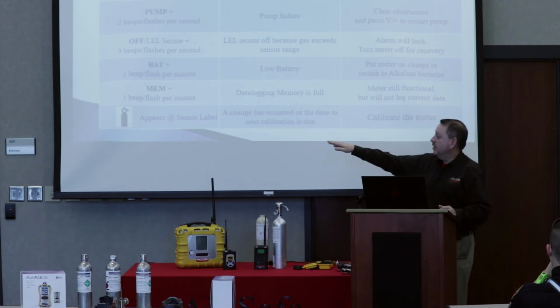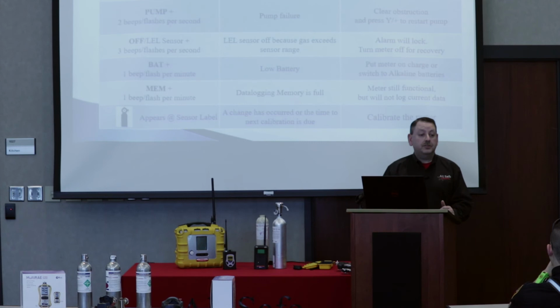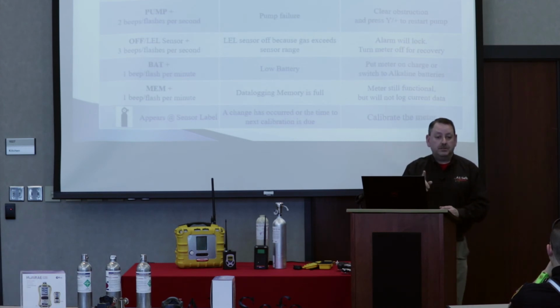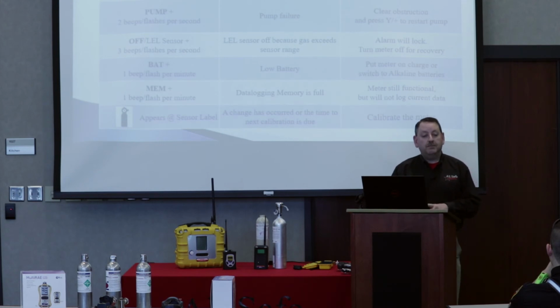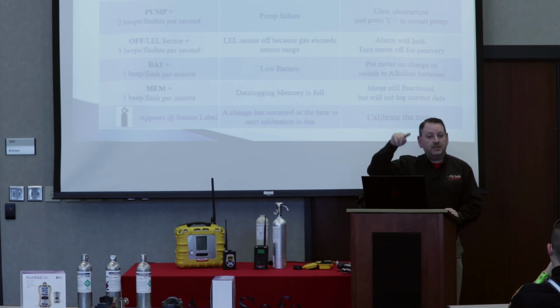And then the last icon here is a little picture of a cylinder. If you see a picture of a cylinder next to any of the sensor names on the face of the instrument, it's trying to tell you that it's either due for a bump check or due for a calibration. So just recognize that. When everything's good to go on the meter, there'll be a big check mark at the top of the screen. Okay?